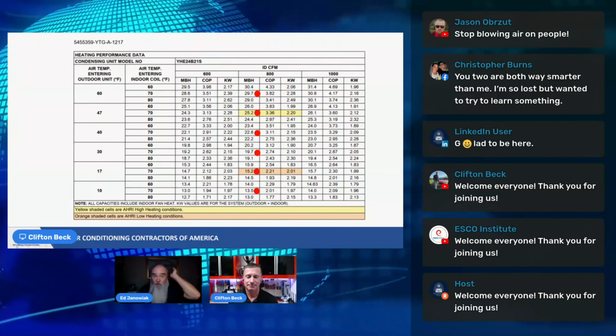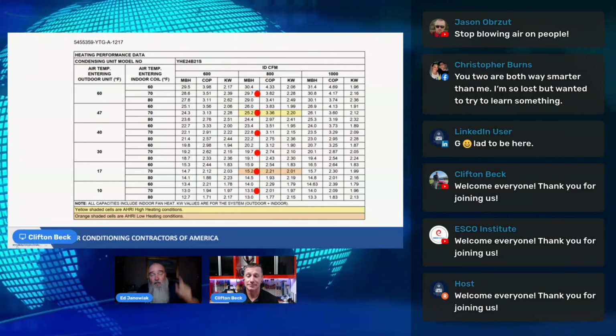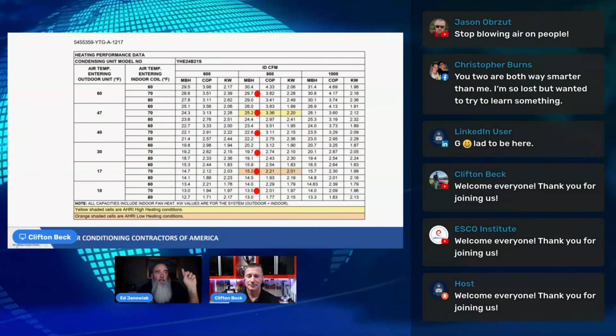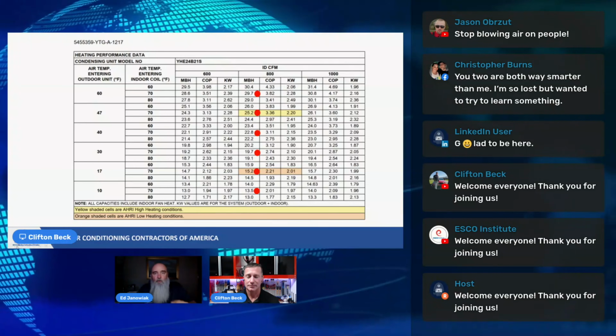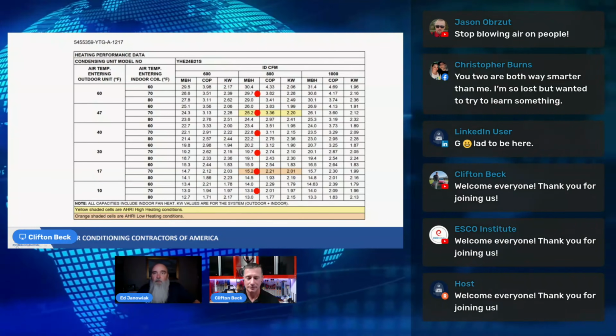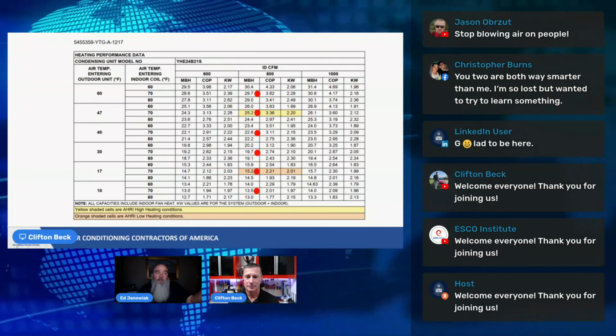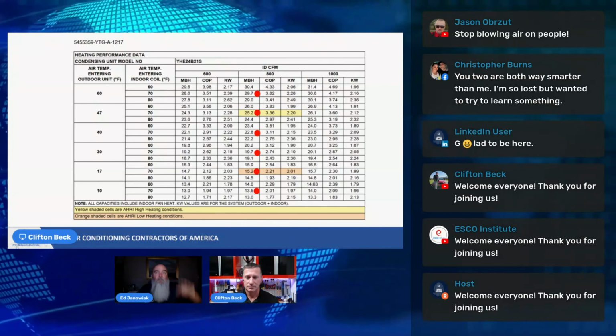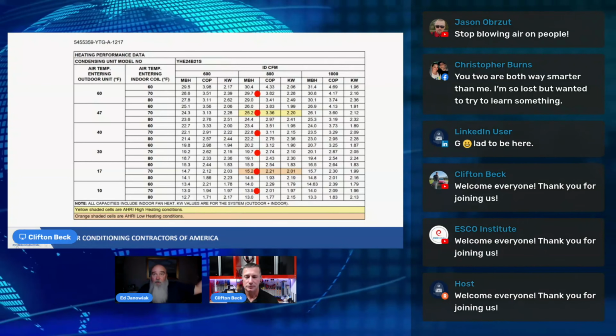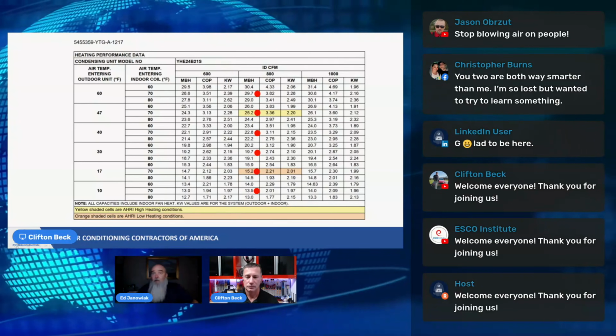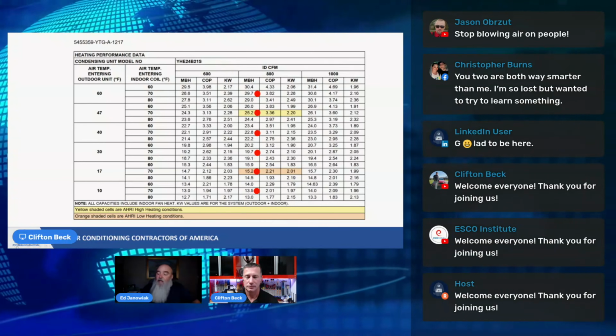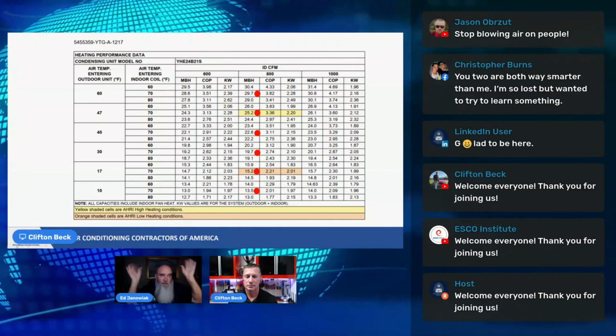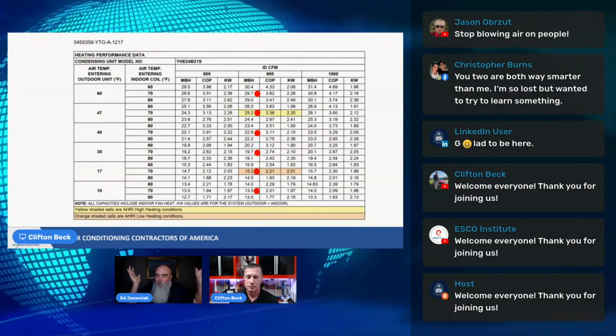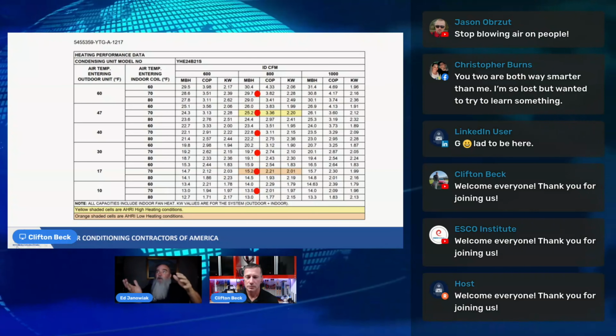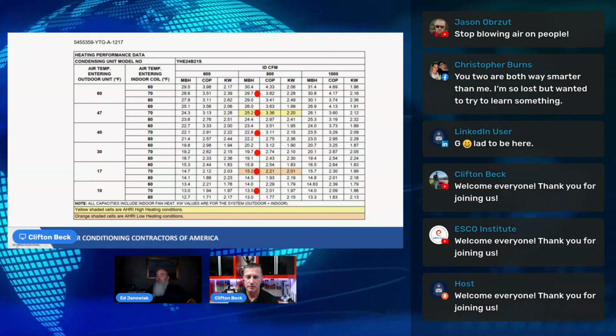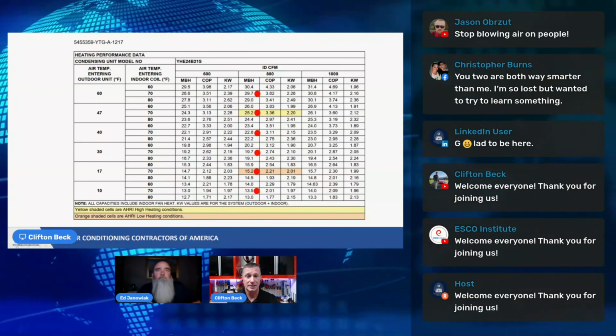Now, you want to know what the proper answer for that is? The closest you can get your heat pump airflow to your cooling airflow, that's the winner. If you're going to end up at 400 CFM per ton, run your heat pump there. If you're running at 450, run your heat pump there. At 350, run your heat pump there. The idea behind all that is less monkeying with dampers and more uniform airflow patterns summer and winter. Absolutely. No, it makes a lot of sense, Ed.